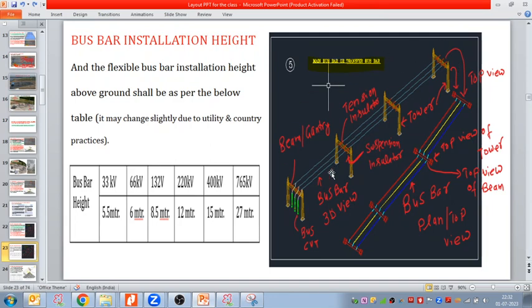Now coming to the installation height drawing, the installation height of the bus bar. The flexible bus bar installation height above ground shall be as per the below tables. Whatever height we are going to see, that generally we follow in India, but it may change slightly due to utility and country practices. So please check with the country and the specific project what their practices are, what practice that country follows for the bus bar height.